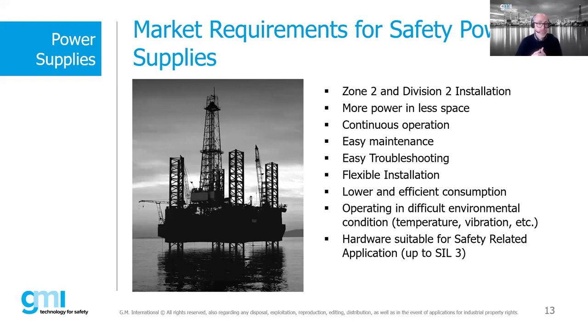The PSS 1250 system meets these needs with an efficiency of nearly 90% and an extended operating range. The system is available up to SIL 3. To meet IEC 61508 requirements, instruments must be able to detect or tolerate under-voltage and over-voltage conditions, and maintain the SIL within the normal operating range. The PSS 1250 is a certified device with both under-voltage and over-voltage protection. Last but not least, harsh environment operation must be addressed.